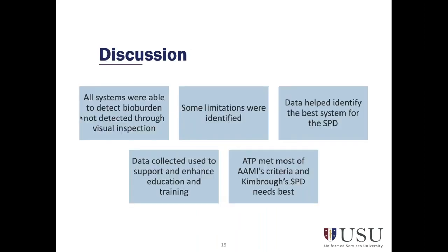Now, all 3 systems demonstrated their ability to detect bioburden in surgical instruments that was not detected through visual inspection. However, it is essential to remember that these systems all have limitations that must be considered before investing in and integrating them into the SPD workflow. These systems are supported by specific markers that limit the spectrum of organisms they may detect. Minimizing workflow disruption in the SPD is crucial, as thousands of instruments are processed daily. Introducing a cleaning verification system that has a minimal impact on workflow is vital to ensure the initiative is feasible and sustainable.